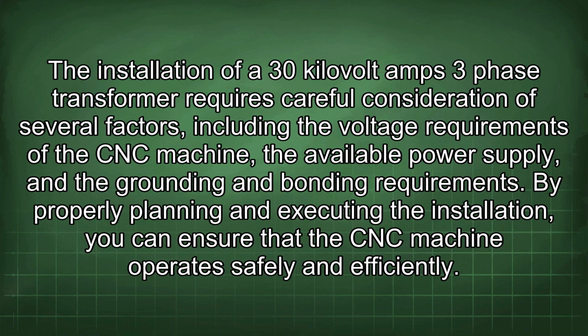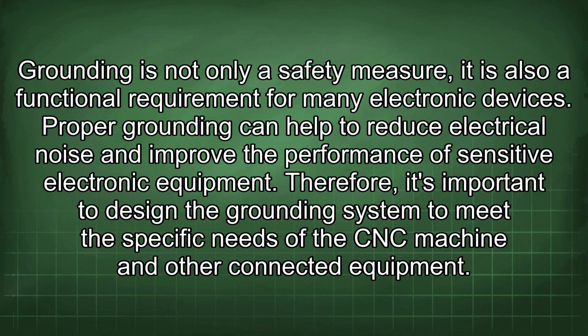The installation of a 30 kVA three-phase transformer requires careful consideration of several factors, including the voltage requirements of the CNC machine, the available power supply, and the grounding and bonding requirements. By properly planning and executing the installation, you can ensure that the CNC machine operates safely and efficiently. Grounding is not only a safety measure, it is also a functional requirement for many electronic devices. Proper grounding can help to reduce electrical noise and improve the performance of sensitive electronic equipment. Therefore, it's important to design the grounding system to meet the specific needs of the CNC machine and other connected equipment.